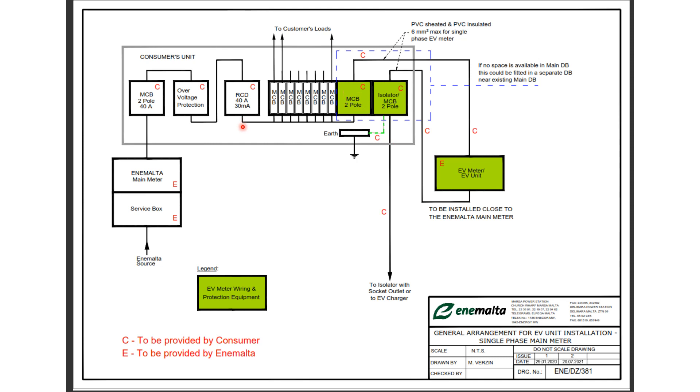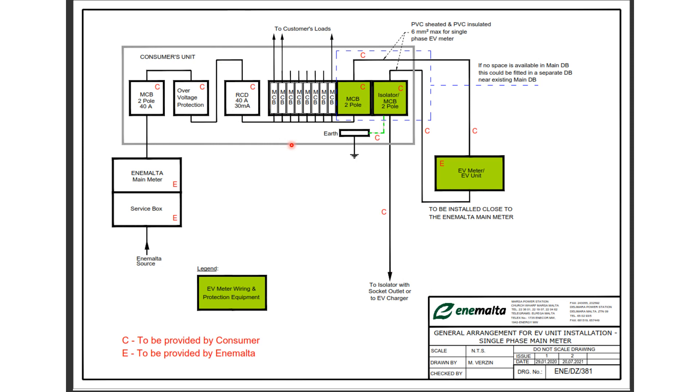So getting an RCBO of type A, you connect to this particular point so that any leakage current from the EV charger would not be summed up to the rest of the installation, but it would be protected with a different residual current device with 30 milliamp of protection. And that is still legal, you still have current protection, you still have overload protection and switching capabilities.